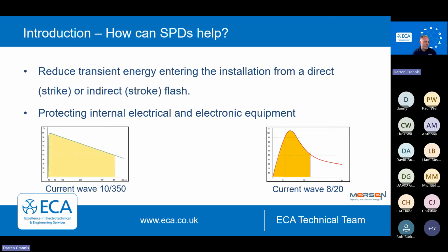So what are the differences between the two? Again, lightning protection, BS EN 62305, and the reason we talk about this in our standard is where lightning protection systems state that they need a Type 1 SPD. We need, as electrical contractors and designers, to put that into our systems.